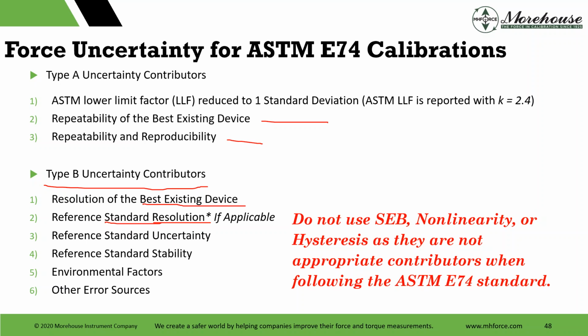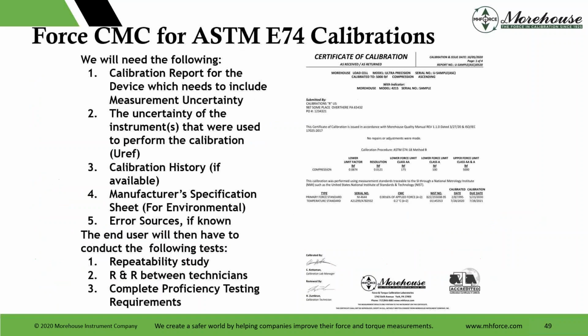Then you're going to take the reference standard uncertainty and stability. Remember, we talked about drift. These are all other things. Stability can be a type A depending on how you use it. And environmental factors such as temperature, other error sources, maybe some side loading and some other stuff. You're going to take all of this stuff and run it through the Welch-Satterthwaite equation. And if you're going to do that, you're going to need a calibration report for the device, the uncertainty of the instruments that were used to perform the calibration. They're right here. This is why we do this. We put these all there.